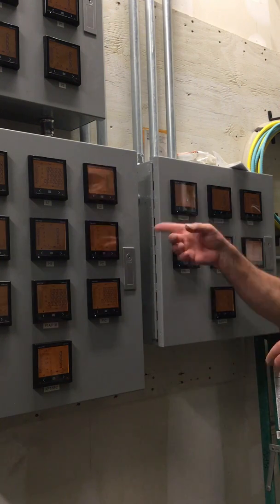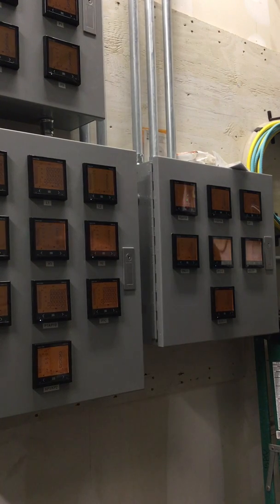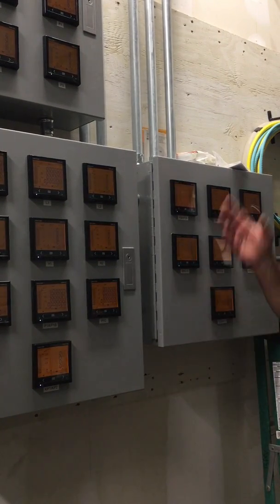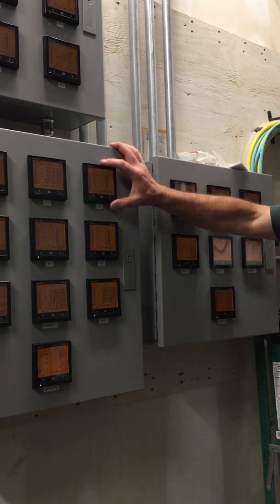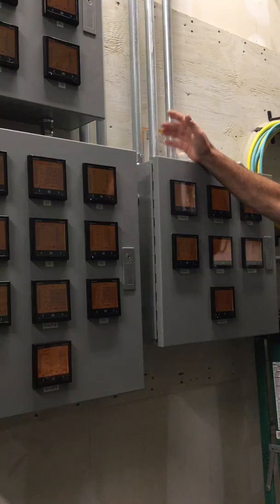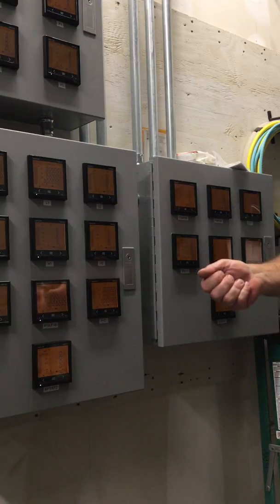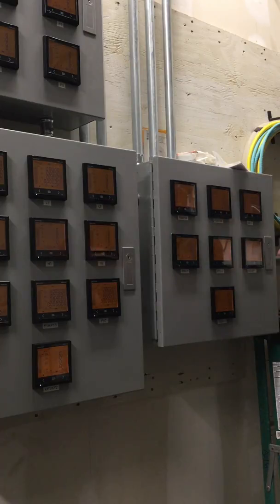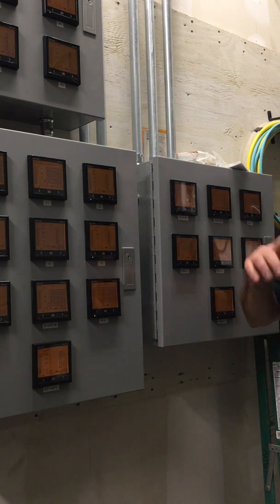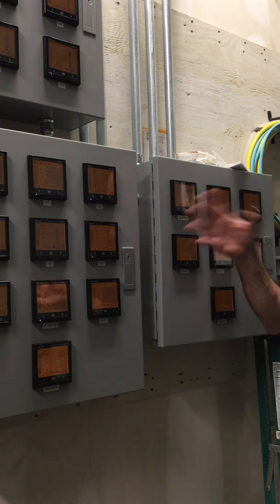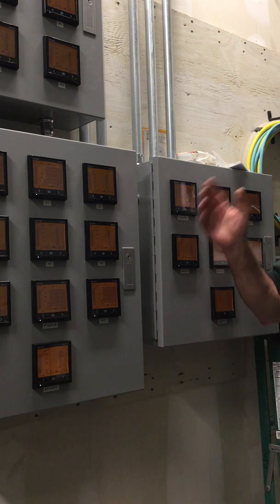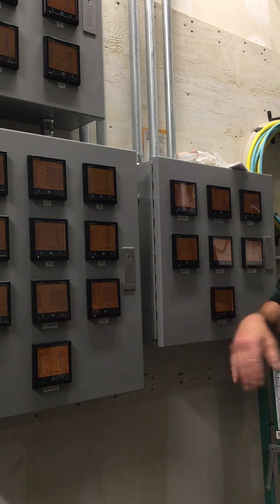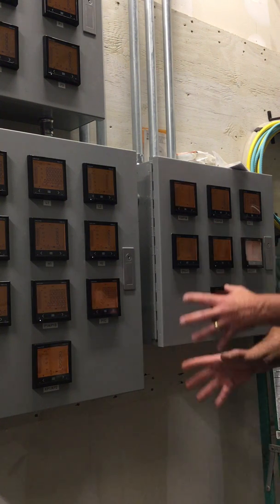What else? Okay, current transformers that are connected to the meters, around the phases that are in the panels or switchboards, wherever they are: 1% accurate CT. So at this point, the meter being 0.2 and the CT being plus or minus 1%, out of the package it's 1.2%, plus or minus. It's usually on the plus side in terms of accuracy, never on the minus. You can't have a CT that works even better than what it should. But given the wiring to go to the CTs, and a little bit of voltage loss or wire size or whatever, installed it's plus or minus 2%, as is the ANSI standard for sub-meters. If they ever get tested by anybody, they'll probably come out a little bit better, okay? But they won't be any worse.